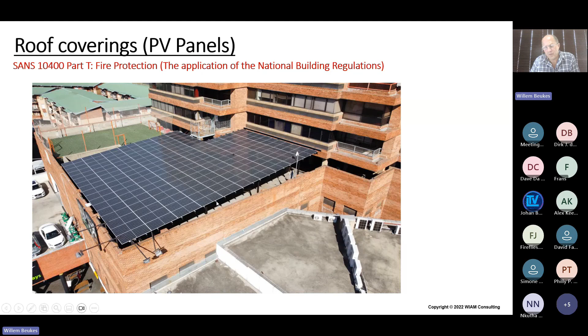When we look at insurance claims happening in South Africa, you have installations being done on roofs, and then all of a sudden you find that the whole roof is gone. And then insurance companies don't understand what happened. In this scenario, when we did a report, it was a combination of where the battery was installed and the DC arc path to the panels, where there was an arc control, and then it burned up the whole ceiling void of the occupation.